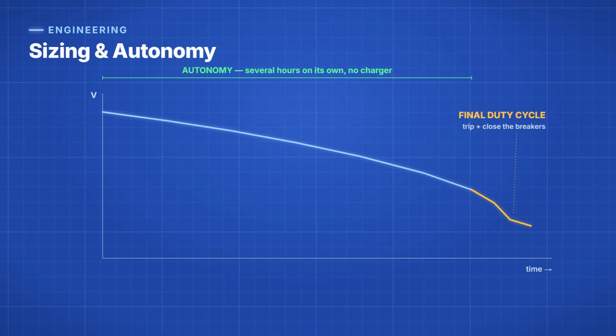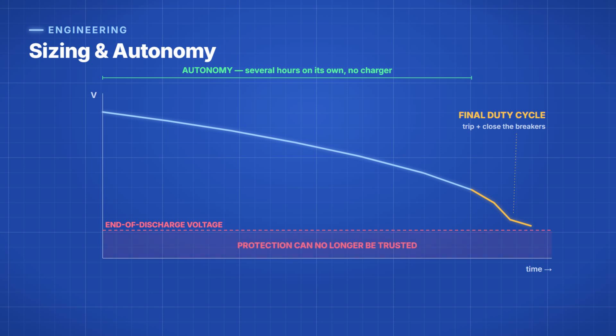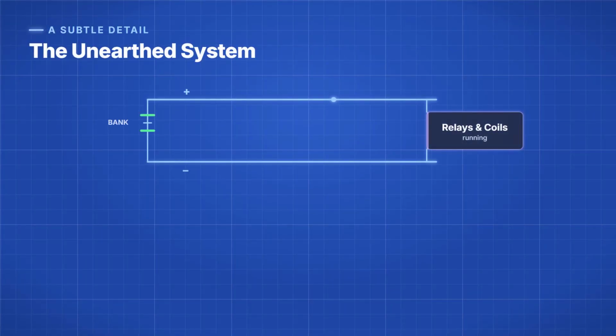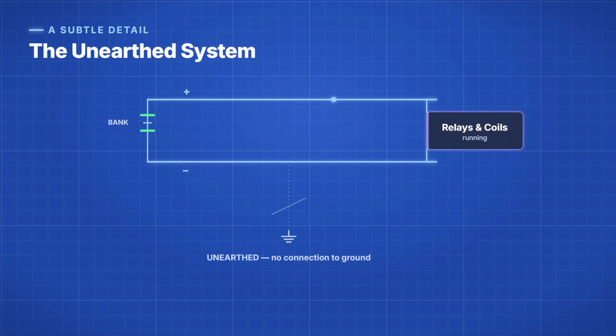Engineers size it down to the end of discharge voltage. That's the lowest the cells can fall to while still operating the relays and coils reliably. Go below it, and the protection can no longer be trusted. There's a subtle but important detail in how the DC system is wired. It is usually left unearthed.